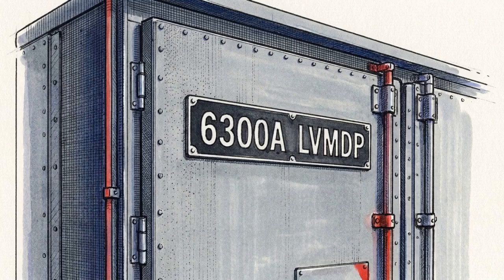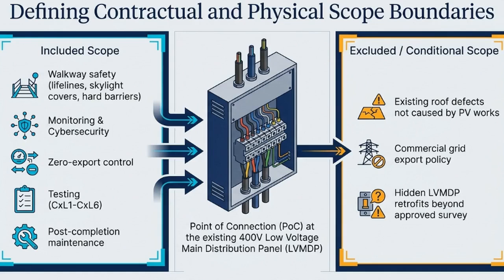For this project, that line is drawn at the point of connection, located exactly at the factory's existing 6,300 ampere main distribution panel. This schematic maps the exact boundary limits. By tracing the engineering backwards from this point of connection at the existing 400-volt main distribution panel out to the solar array, we can deconstruct the physical, logical, and safety architectures of the plant.